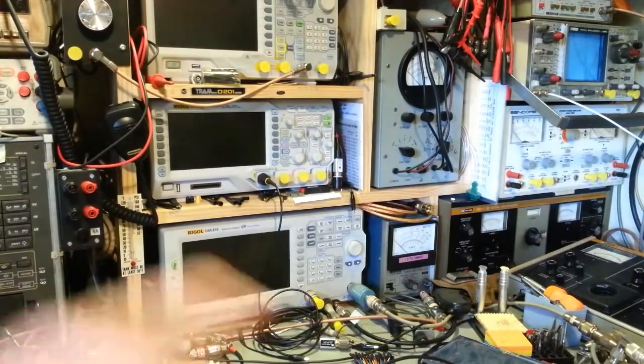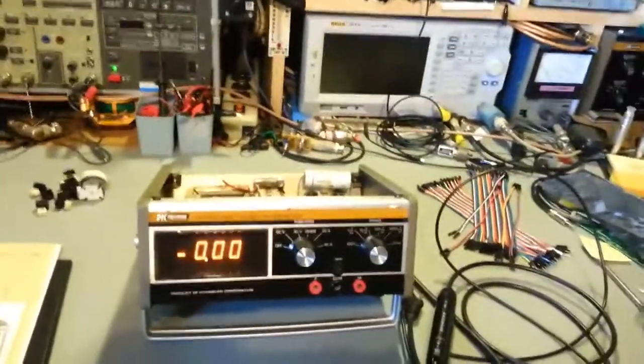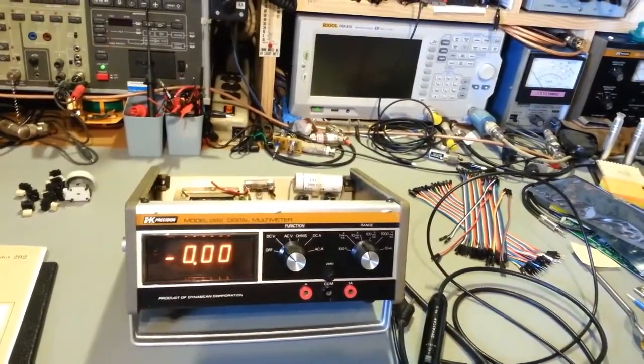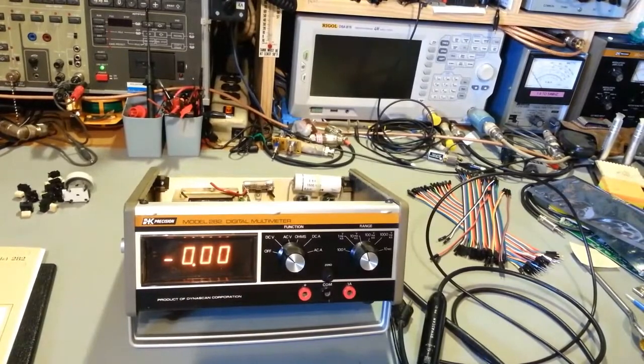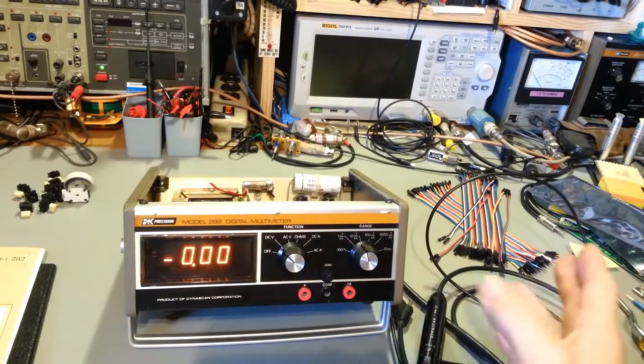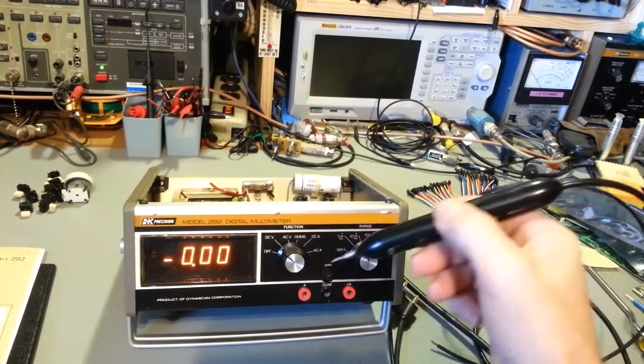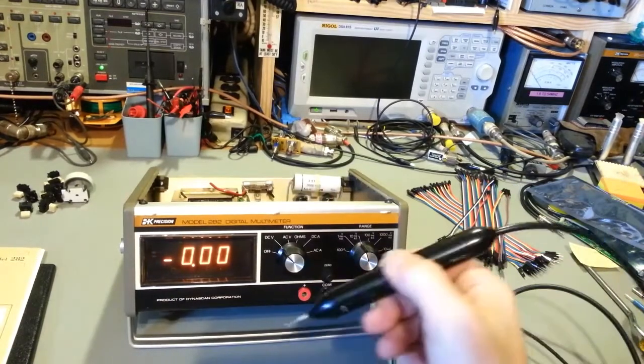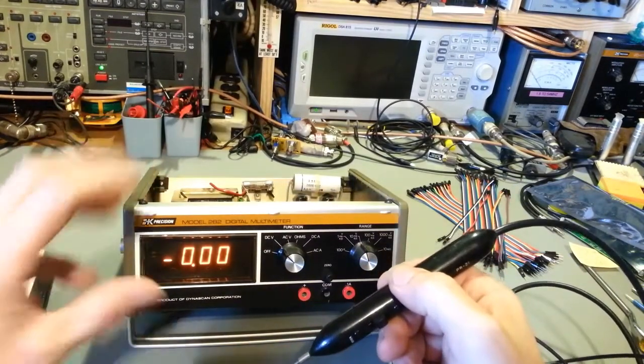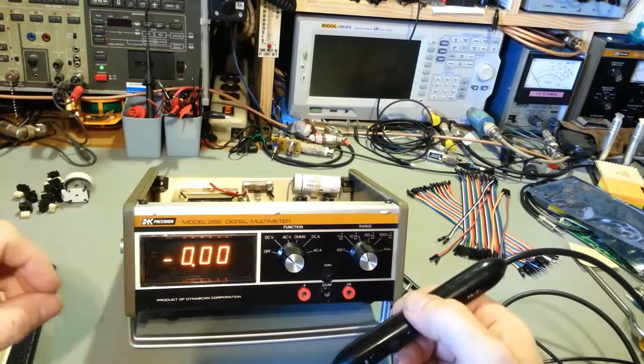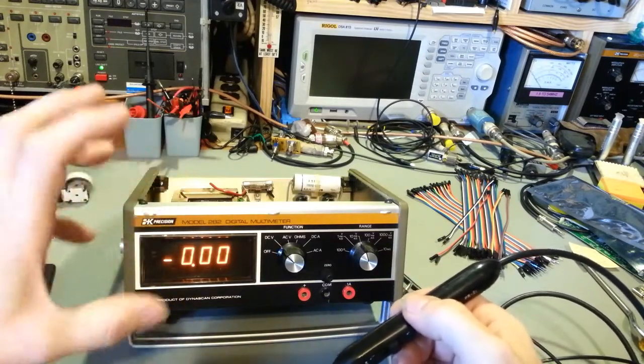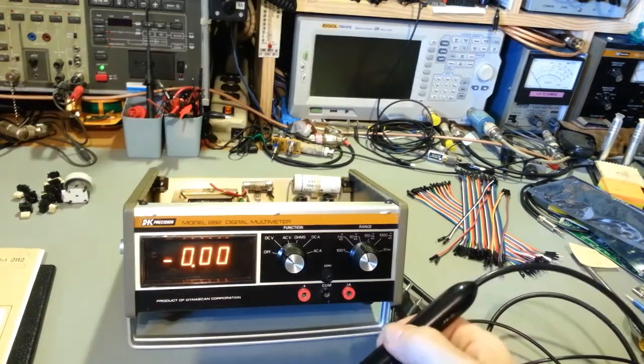Shoot, you can use, yeah, I've got vacuum tube voltmeters for a reason: extremely high input impedance. That's one of the downfalls of some meters, is they have a low input impedance. The problem with low input impedance meters is when you probe the circuit, the meter loads down that circuit and the reading will change because the meter is sinking a lot of power away from the circuit.